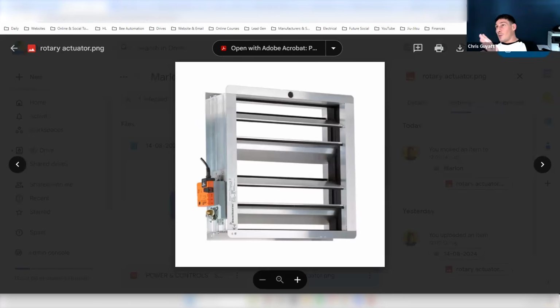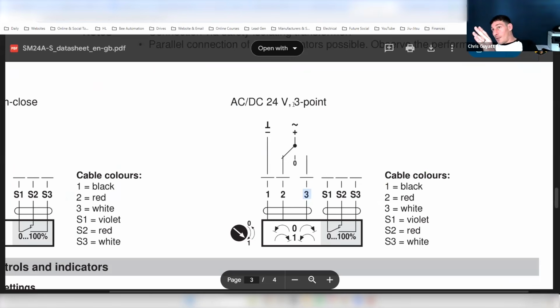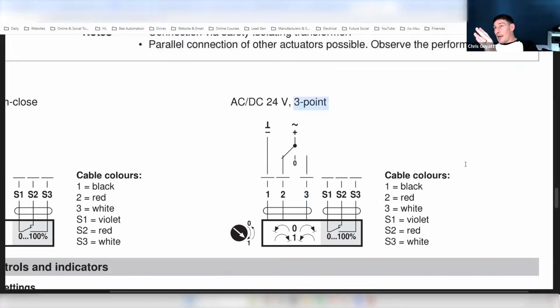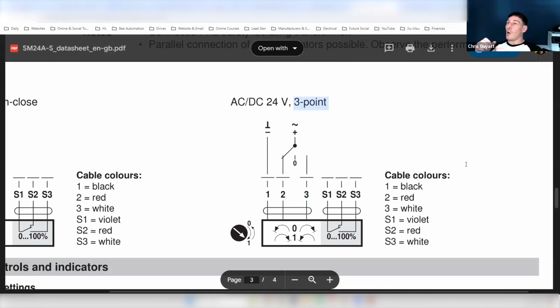So on this 3-point control, it's not fully open or fully closed. We can basically modularly control it by applying power for a certain amount of time to open it to a certain percentage or close it to a certain percentage.